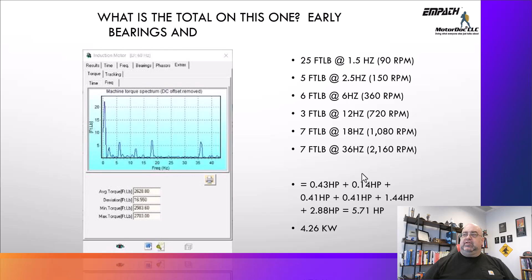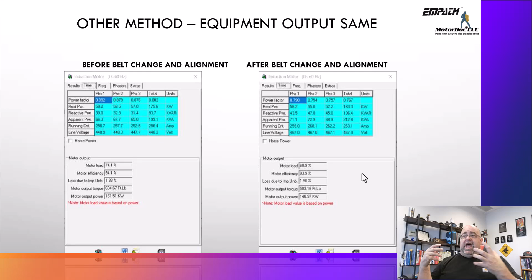If I don't have anything else going in there, all I have is a power analyzer, I can do kilowatts before and after. Take your measurement before, I don't care if it's a Fluke or whatever else. You take your power analyzer, get the data, then after take the measurement in the exact same load or as close as you can.